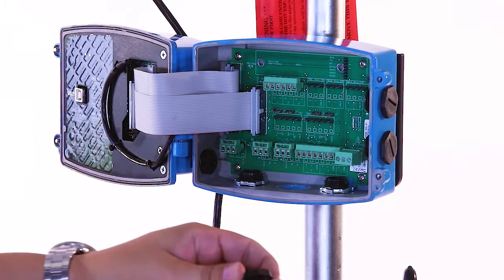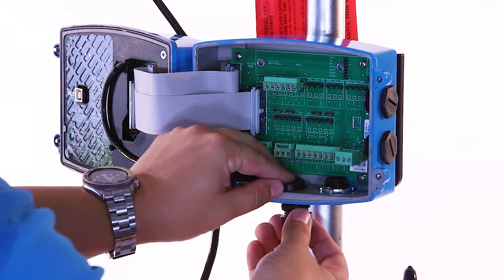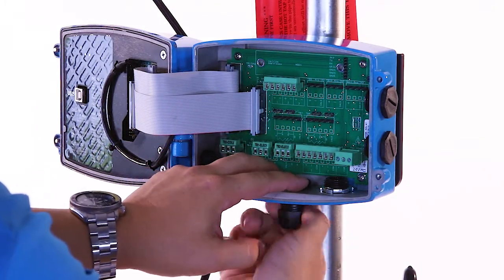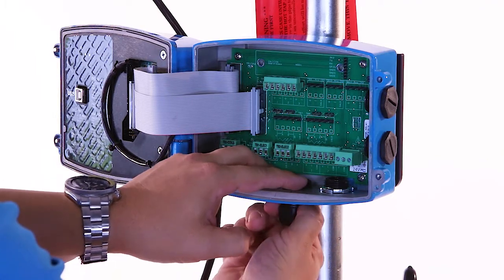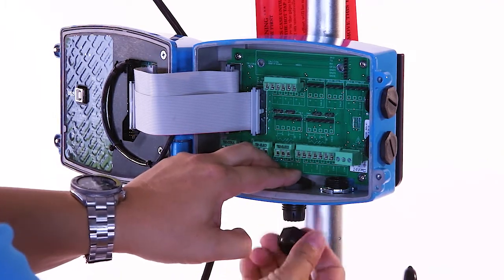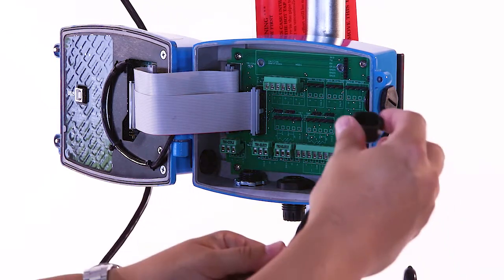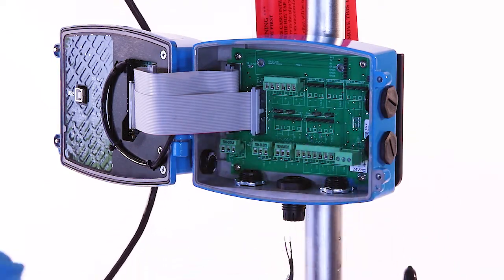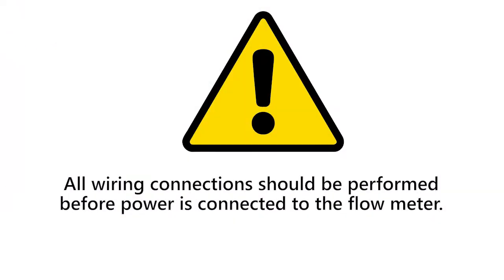The electrode and coil wires are pre-attached via pluggable terminal blocks inside the flow sensor enclosure. Attach the strain relief fitting provided with your meter, then route the electrode and coil wire cable through the fitting into the transmitter enclosure. Caution: all wiring connections should be performed before power is connected to the flow meter.